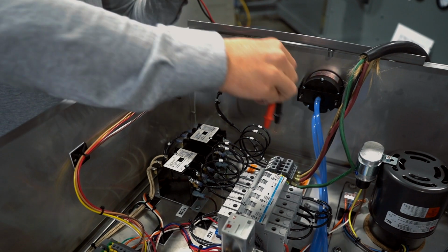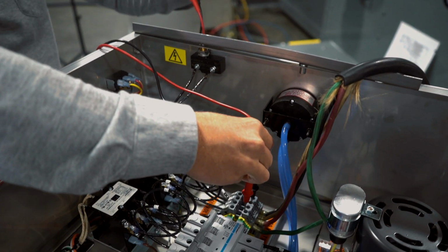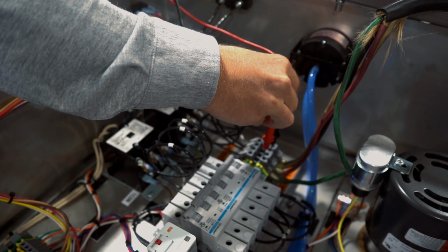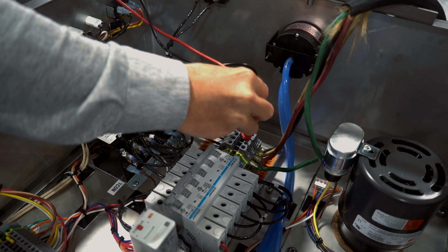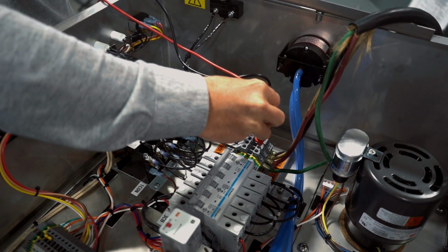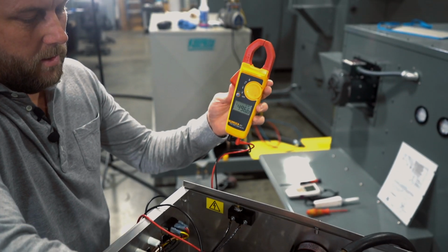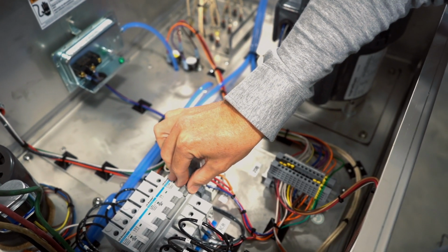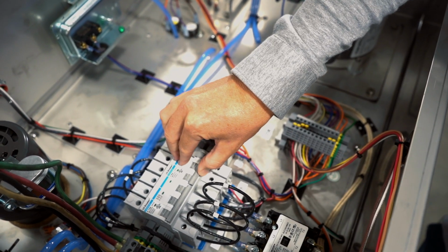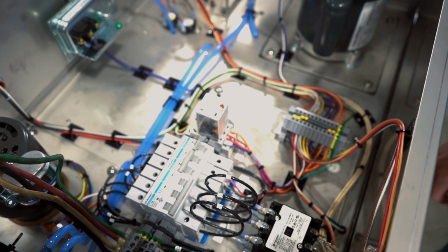We also will measure between L2 and L3 carefully. And we should also have 495, 496 volts. Now that we've got power, we can turn on the single pole breaker as well as the 2-pole breaker for the transformer.